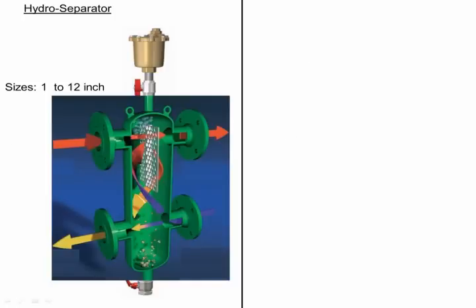Why? Because when you have pumps turning on and off on your primary, and perhaps one or more pumps turning on and off in your secondary, you're going to have almost always different rates of flow on your primary versus secondary. So if your primary has more flow than your secondary, there's going to be a flow component going down from the boiler back to the boiler in this direction if you have a heating system. Same thing on the secondary. If your flow rate in the secondary is higher than the primary, even momentarily, your flow will go up this way. So the baffle plate becomes a flow straightener.